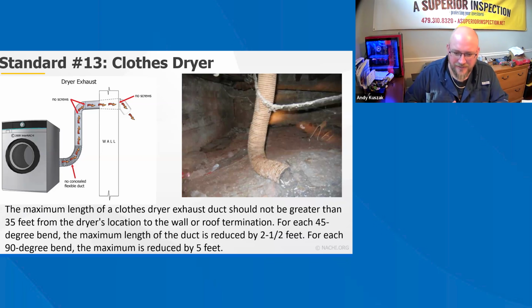With the plastic dryer vents, the PVC or SDR, when the air comes out of your dryer, it's very moist and there's a lot of lint in it. As it goes down all the way to the end, it starts to dry out, and because it is moist, it starts to adhere to the other dryer lint and to the walls of the plastic pipe. As that travels through, it creates a static charge, and that static charge could ignite at some point. That's exactly the reason why PVC and SDR is no longer acceptable to use as dryer vent extensions. But like I said, we see them here. Any house that's 10 years or older is more than likely going to have a PVC or SDR dryer vent. So keep an eye on that.